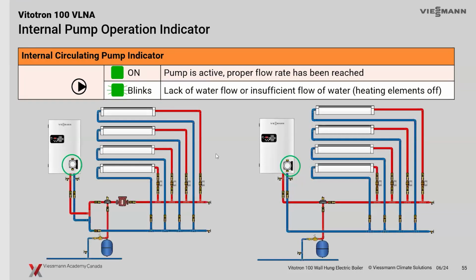If there is some issue, like a lack of flow, maybe you've got some glycol in your system and we've got a bit of a slug because it's a colder day, and that pump icon is blinking, that's going to let you know we've got a lack of flow right now. It will try, and once that flow rate gets up to operation, it will stop blinking and go back to solid. But if you have multiple zones and a high pressure drop in one of those zones that we weren't accounting for, and that one zone calls, you start seeing blinking on the pump. That could tell you there's too much pressure drop in that particular zone, and we can't meet our minimum flow rate. You get that little icon.